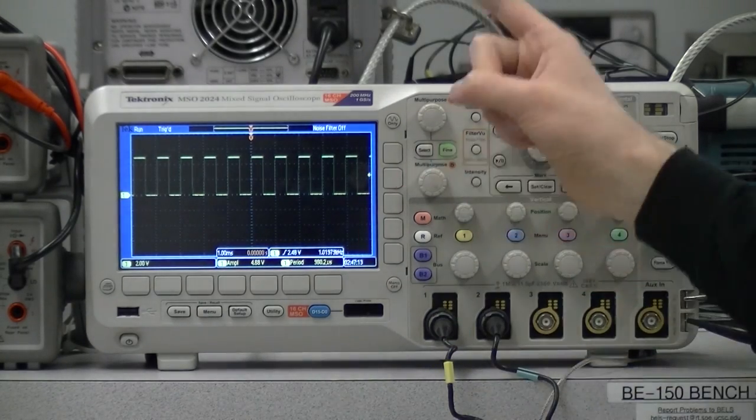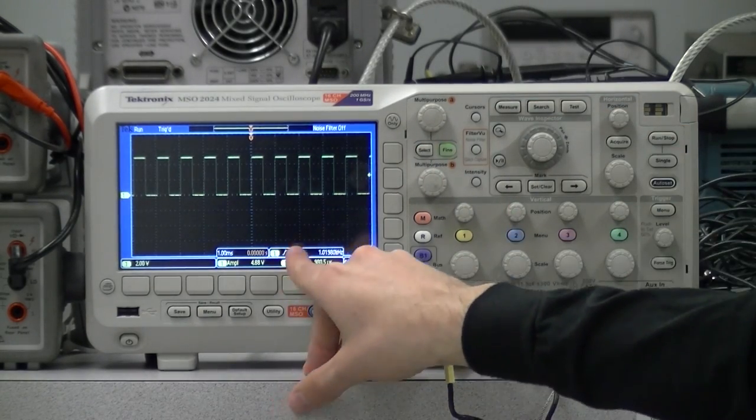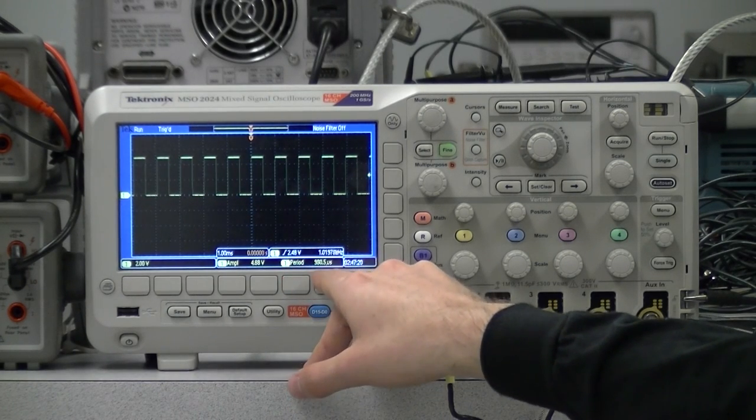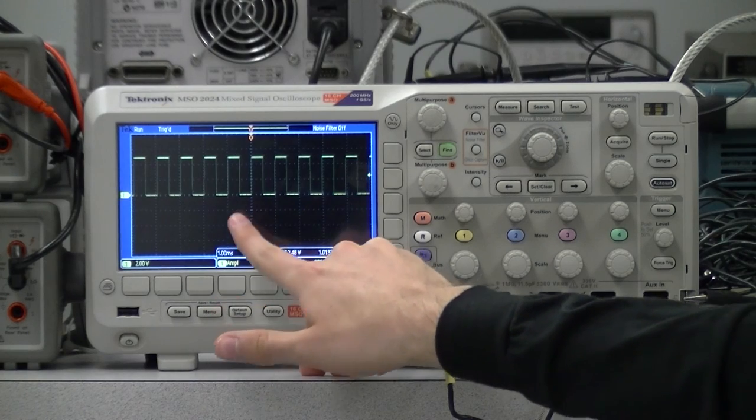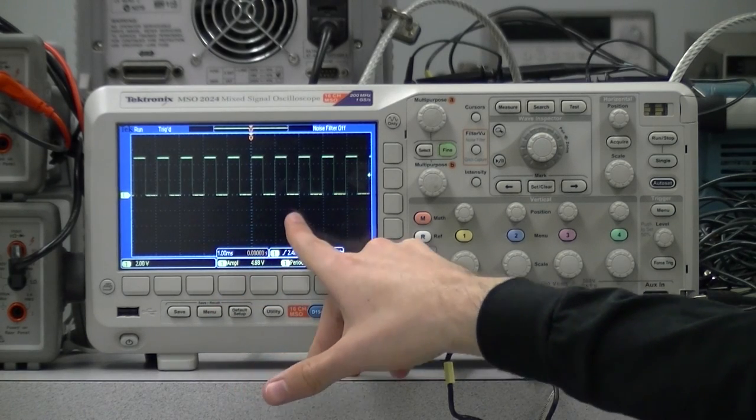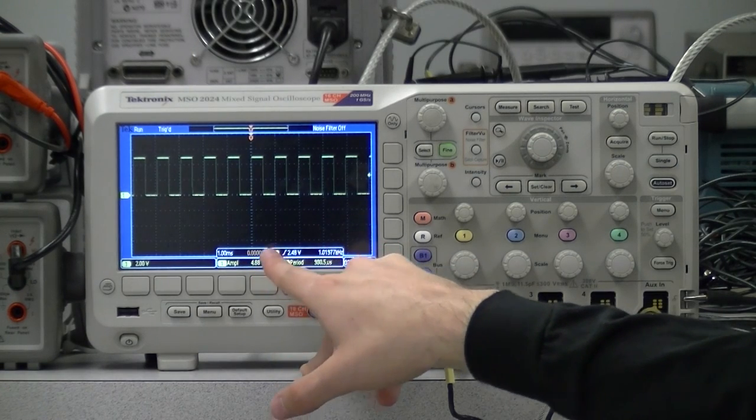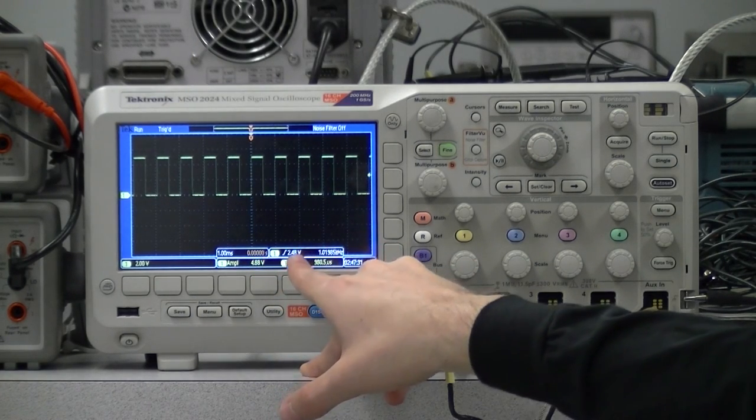We have to press it once for each menu we want to close. We can now see here that the period is reported as about 980 microseconds, and the amplitude as 4.88 volts. If the scope were perfectly calibrated, this would be 1 millisecond and 5 volts, but these have not been maintained in about 15 years.